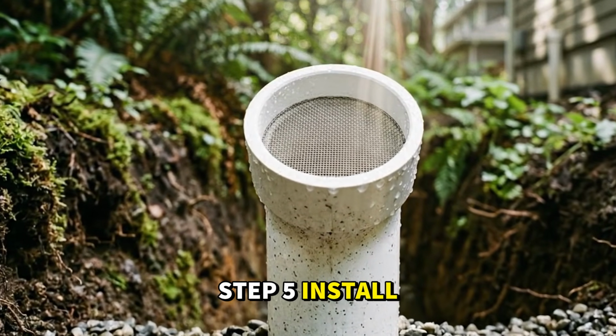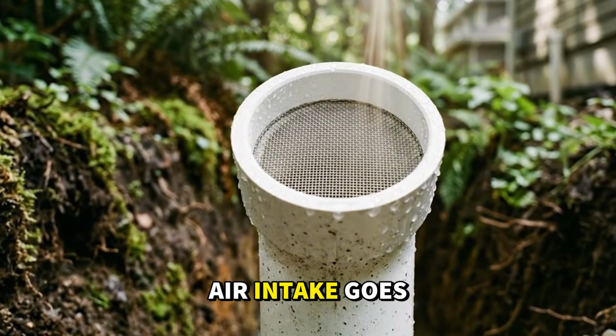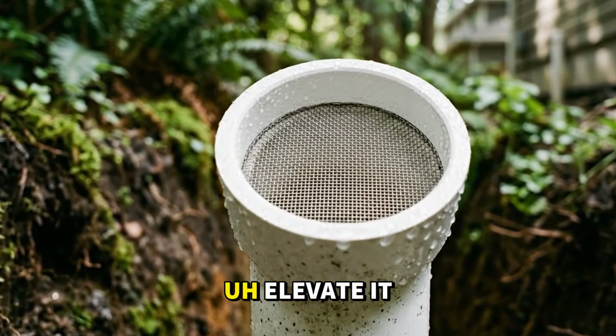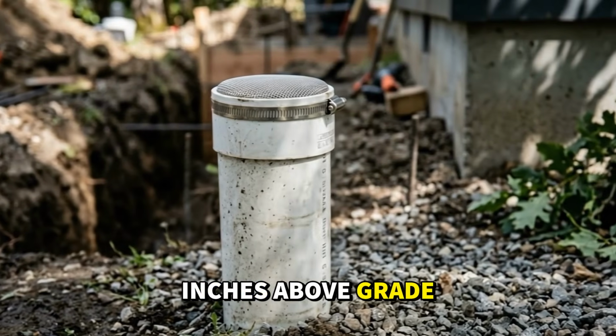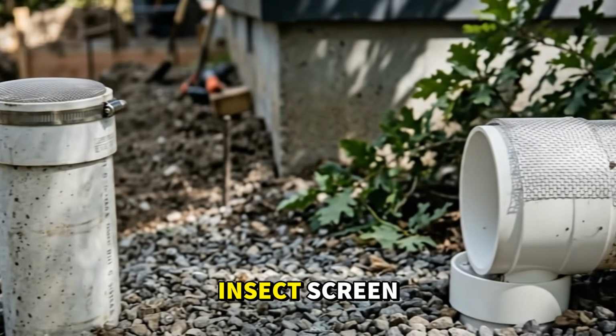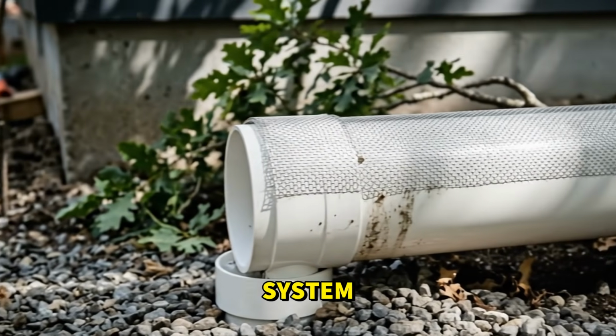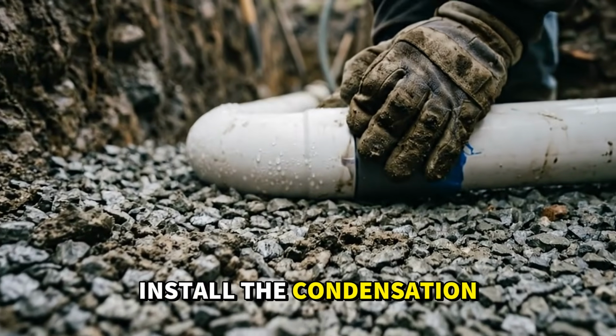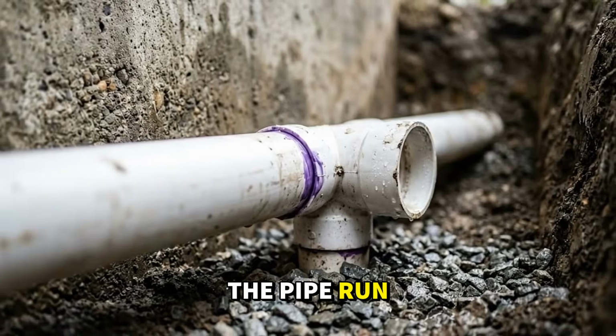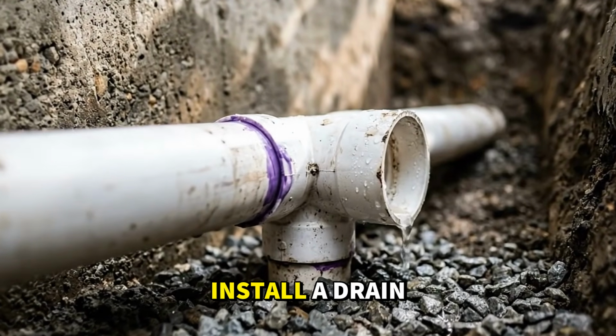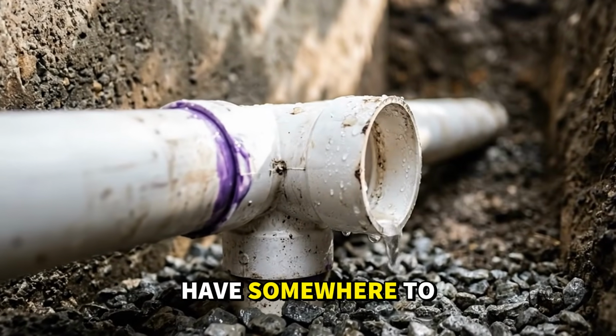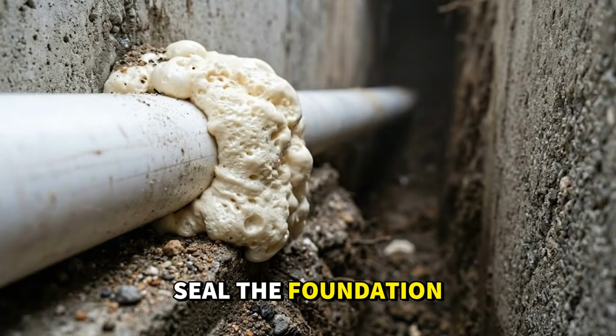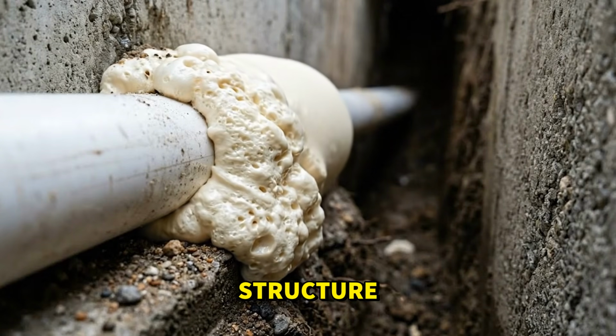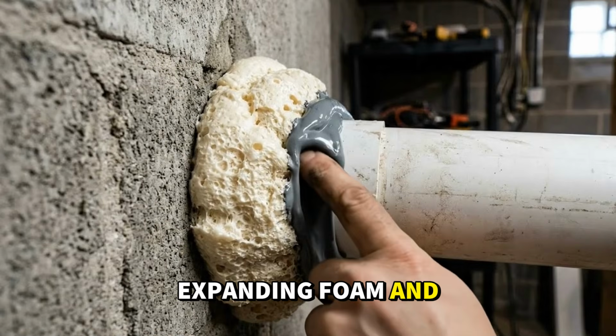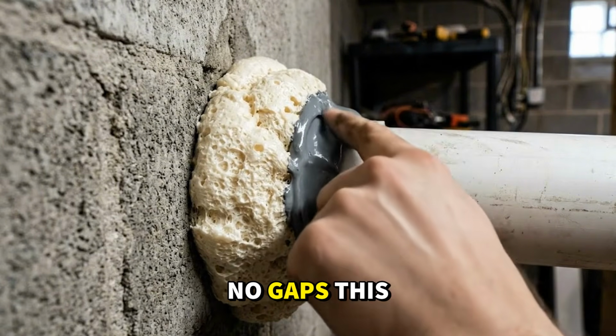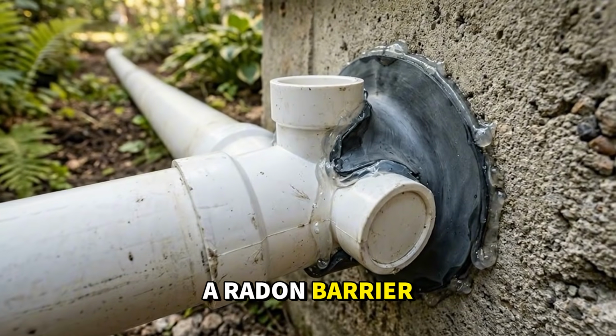Step 5. Install the inlet. The above-ground air intake goes on the shaded north side of your property. Elevate it at least 18 inches above grade. Install a galvanized or stainless steel insect screen. This is where air enters the system. Step 6. Install the condensation drain. At the lowest point of the pipe run, typically where it meets the foundation, install a drain fitting. Condensation must have somewhere to go. Step 7. Seal the foundation penetration. Where the pipe enters your structure, seal it completely, expanding foam and exterior grade caulk. No gaps. This is both an air seal and a radon barrier.